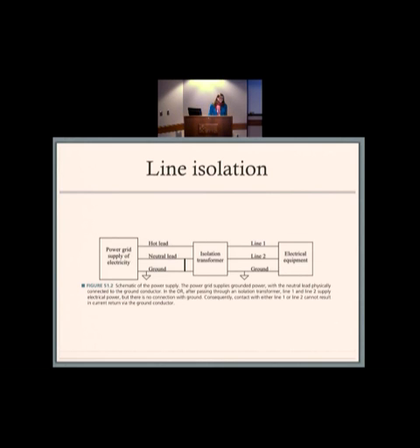There are alarms in the operating room - you'll be able to find where they are. They're supposed to detect the amount of current leaking from various pieces of equipment, and if it gets too much, the alarm goes off. But it doesn't cut the power off, it just tells you there's a leak somewhere, some faulty piece of equipment, and that means you can get a shock.